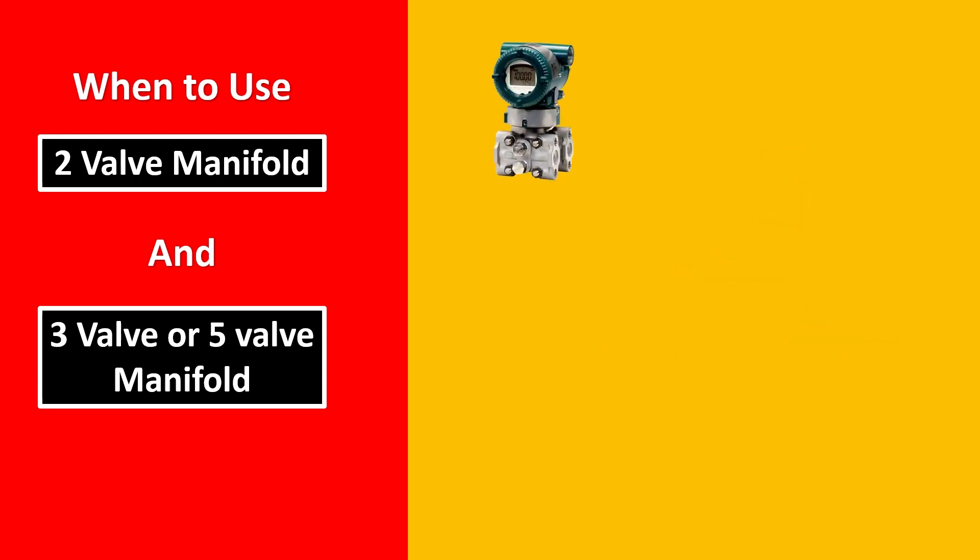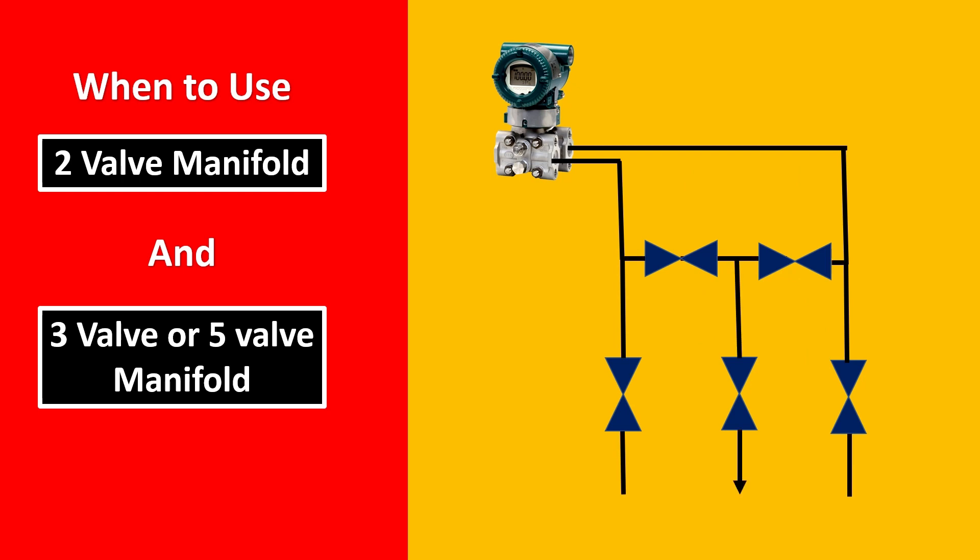But when it gets to a 5-way manifold now here, a lot of configurations are available. This is one of the most used configurations. Here you would keep the, remember the 2 extreme sides are always open and the middle 3 work together. So the middle 3 are closed in normal operation. Remember that 5-way manifold is specially used for venting things or draining things. So you have the extra precaution or the extra way to vent or drain. Now here in operation when you want to remove your transmitter, you would have to keep the extreme 2 valves closed. And the middle 3 are going to remain open. So the first 2 would equalize it and the third one would vent it out either to a closed system or to the atmosphere.